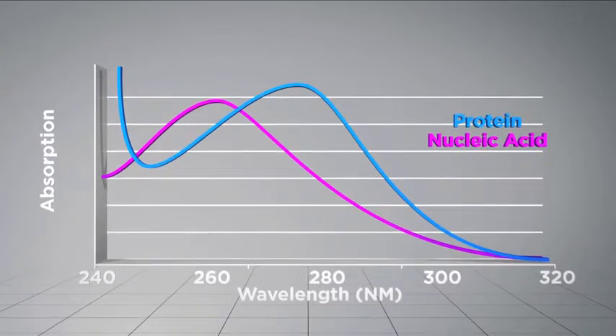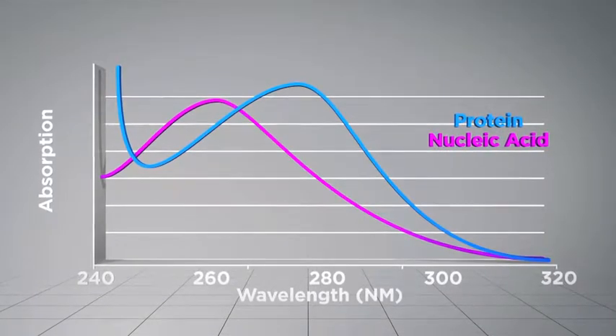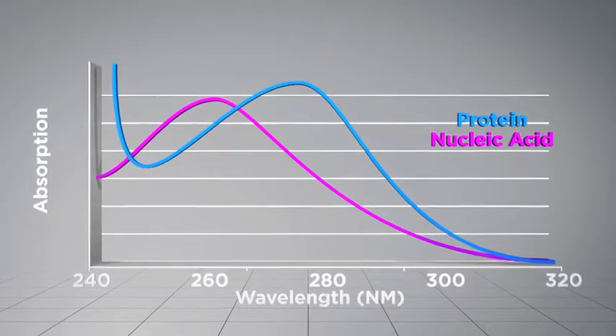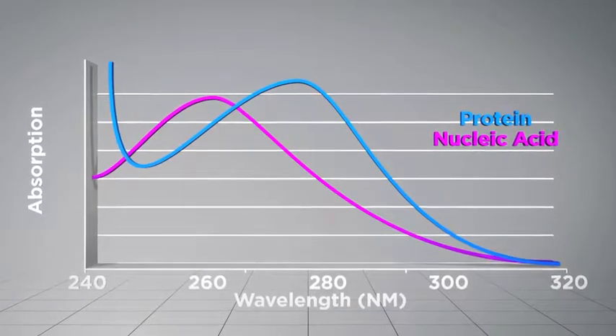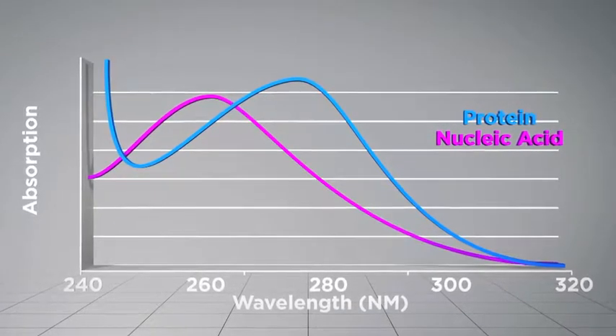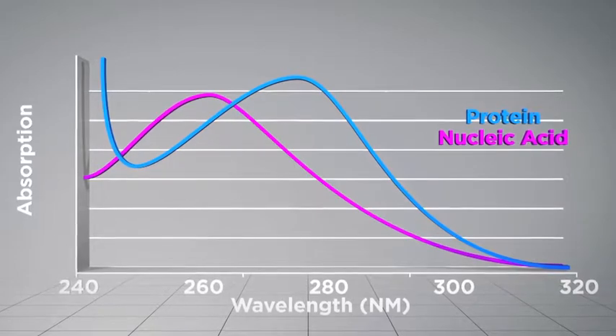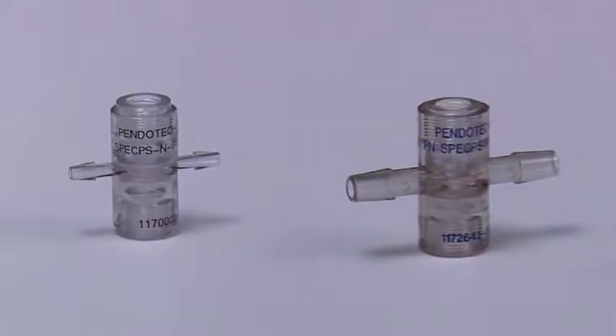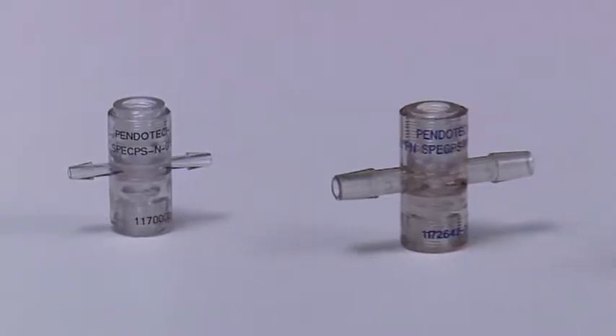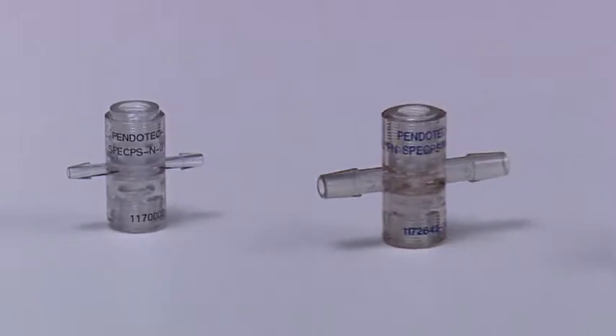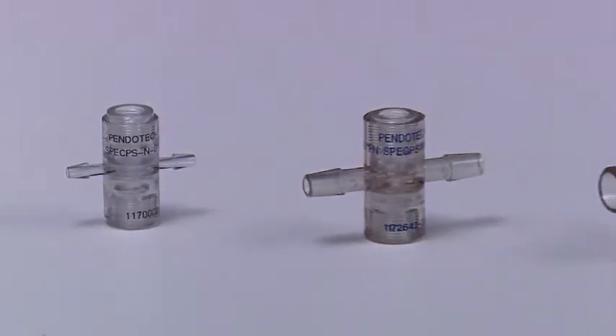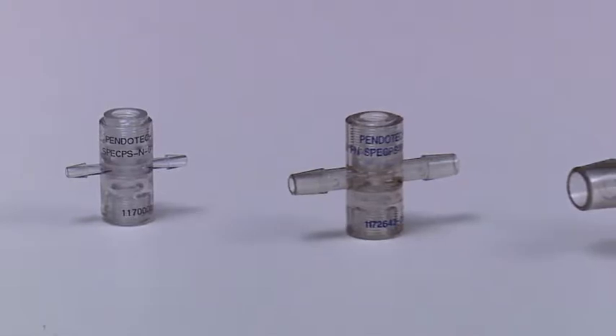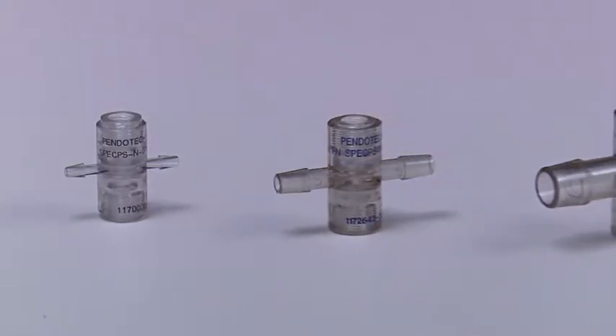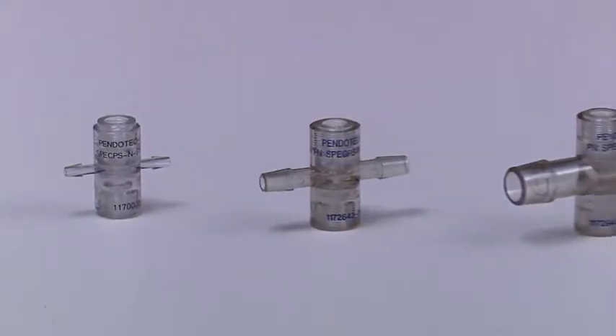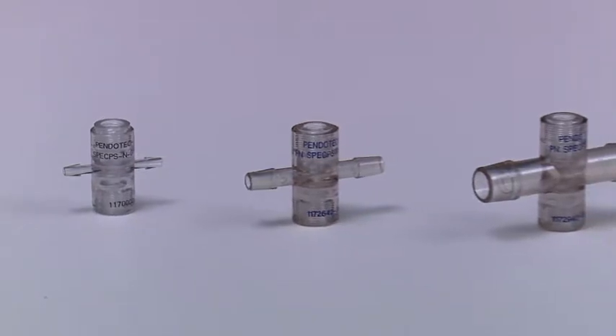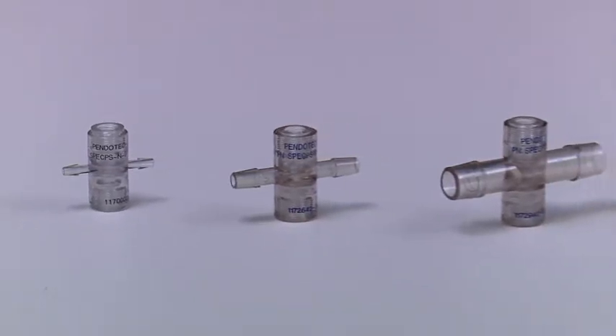Proteins, for example, are often measured at a wavelength of 280 nanometers in a liquid solution, and other wavelengths for other types of molecules. And under the correct conditions, the concentration can be measured. The single-use sensor, in combination with a photometer, monitor, transmitter, enables measurement of liquid within the tube in the range of 0 to 2 absorption units. Their unique properties and features make them amenable for use in many applications in the biopharmaceutical industry.